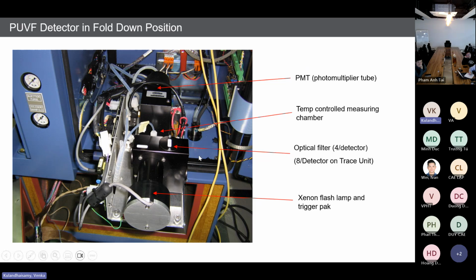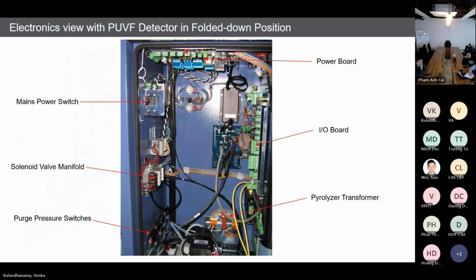Okay, you have seen this part already, the PUVF bench. It consists of a UV lamp with trigger pad, optical filters, then reaction chamber, PMT tube, and then the photo detector at the end. This looks like our electronic chamber. The electronic chamber has all the PCBs, and the PUVF bench is on the bottom side. You see this one, the PUVF bench.